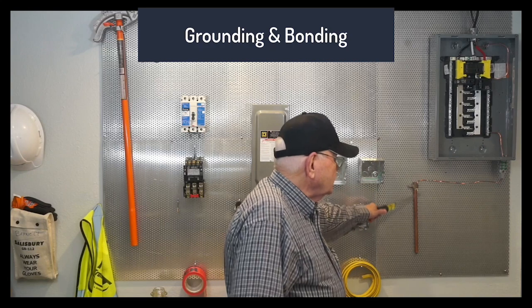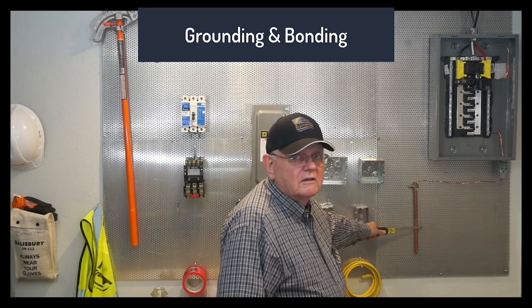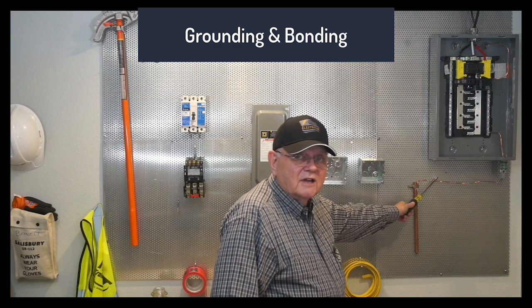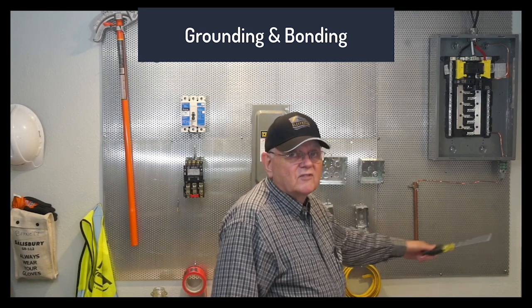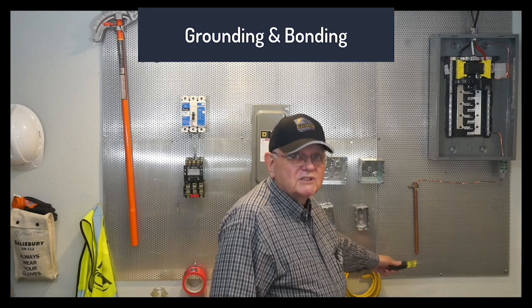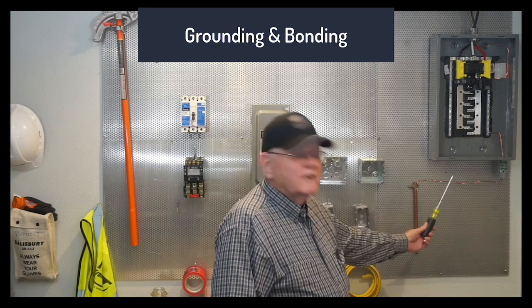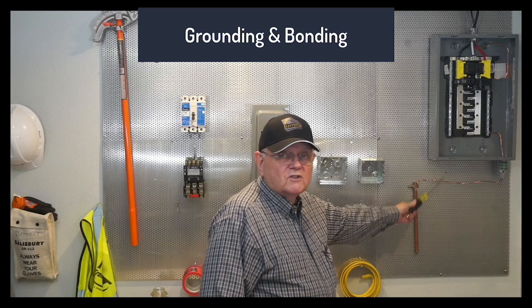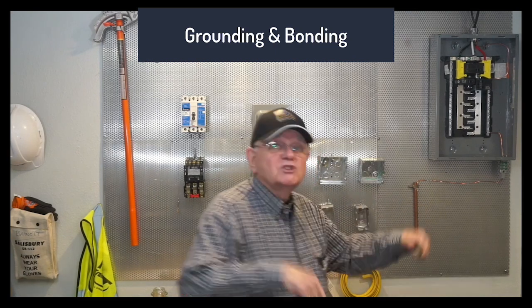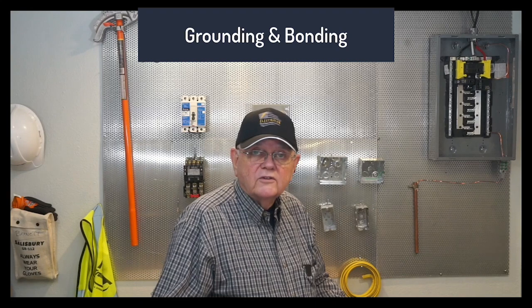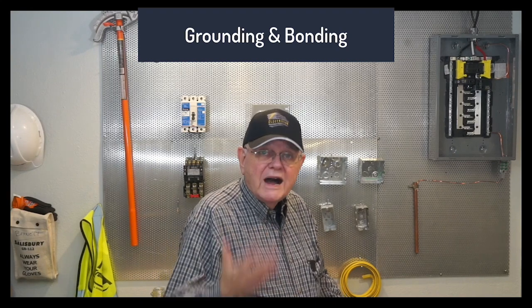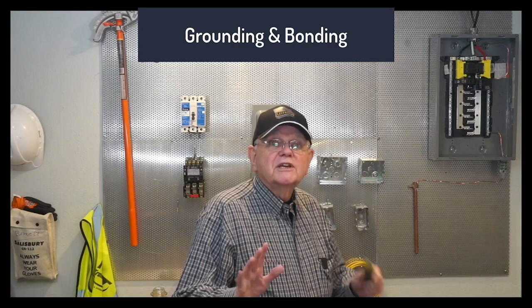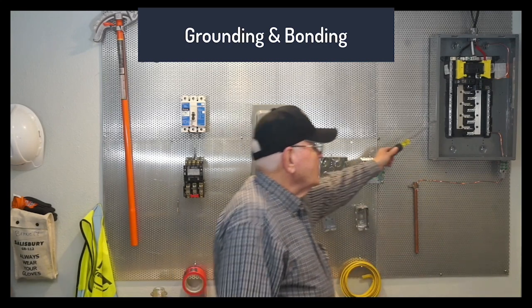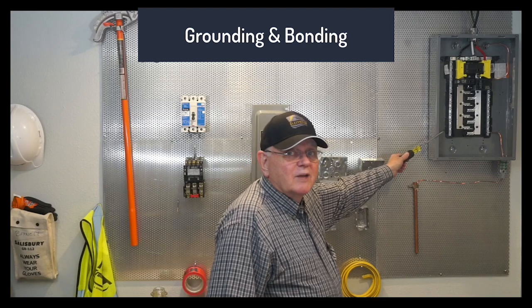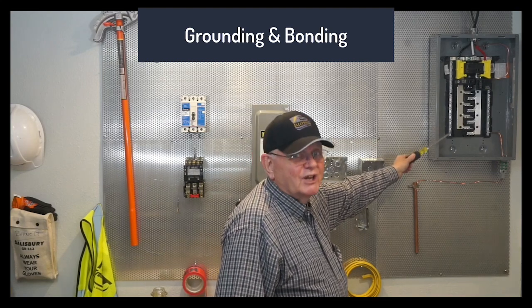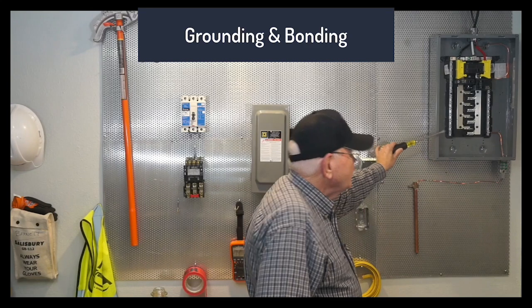If I connect something to the earth, that's grounding. I may connect this grounding electrode conductor to a piece of rebar that's in the concrete. So it extends the connection from the earth up through the concrete where I can connect my grounding electrode conductor. That's ground. I intentionally connect to the earth. That's grounding. Now, bonding I use for protection against ground faults. Any metal component that's likely to become energized during operation, we saw a new definition for that, okay? I have to bond to it.